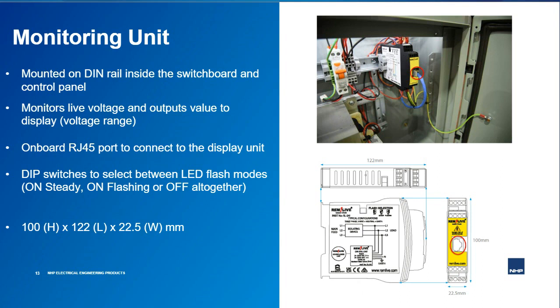The monitoring unit also includes dip switches located at the side of the unit. These switches are used to control the flash mode of the two banks of LEDs at either side of the door display unit, which indicates as soon as the REMLIVE monitoring base unit detects the minimum specified potential difference between any two connected conductors. The LED flash modes are on steady, on flashing, or off altogether. The position of the dip switches for each mode is represented on the label found on the side of the product, and I've circled this for your reference.